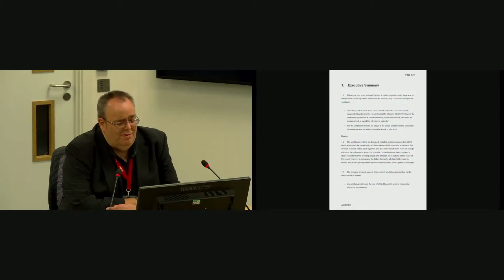Yes, to a point. The psychrometry of air and the method in which a chilled beam works will always produce an elevated risk in terms of condensation, which can lead to fungal spore proliferation or bacterial proliferation. So whilst they weren't explicitly excluded, recirculating air conditioning units were not recommended in any clinical areas as far back as HTM 2025. So the inference, if you will, whilst chilled beams weren't specifically noted as not being appropriate, there was certainly evidence back in the 90s that they had risks associated with them.